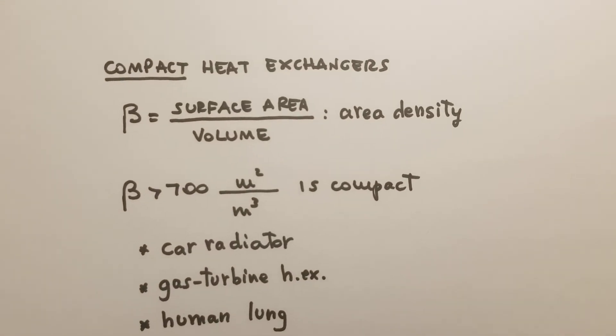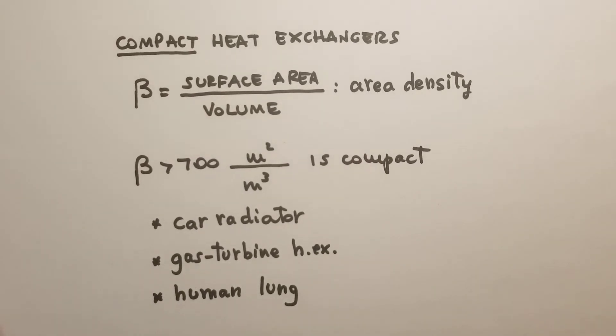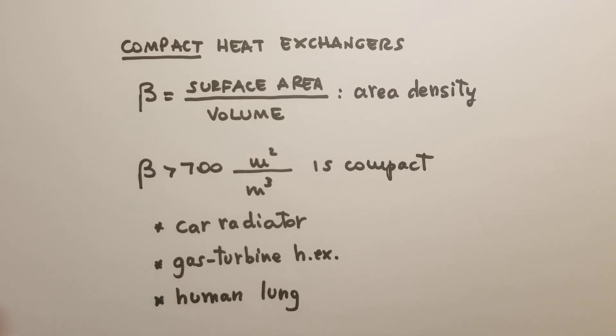An important quantity in engineering design of heat exchangers is the area density beta. This is important to quantify whether a heat exchanger is compact. The area density beta is defined as the ratio between the surface area through which the two fluids exchange heat and the volume of the heat exchanger. If beta is larger than 700 meters squared divided by meters cubed, then the heat exchanger can be defined as compact.